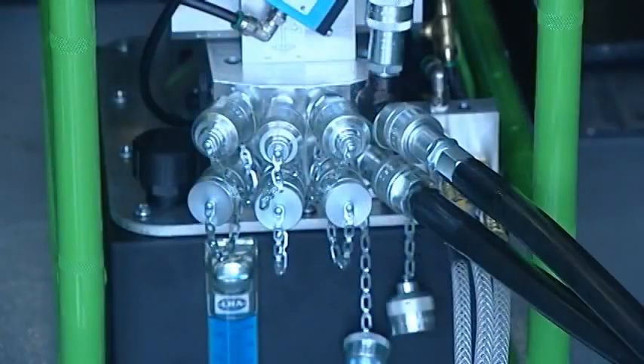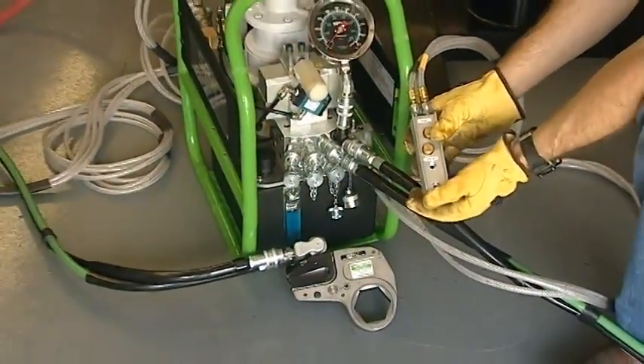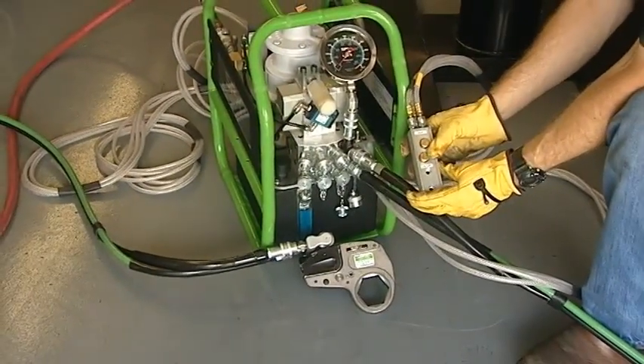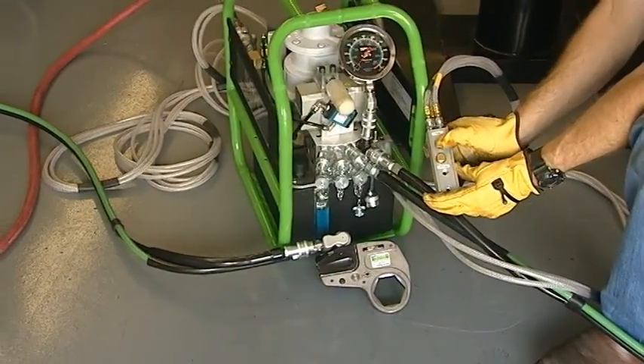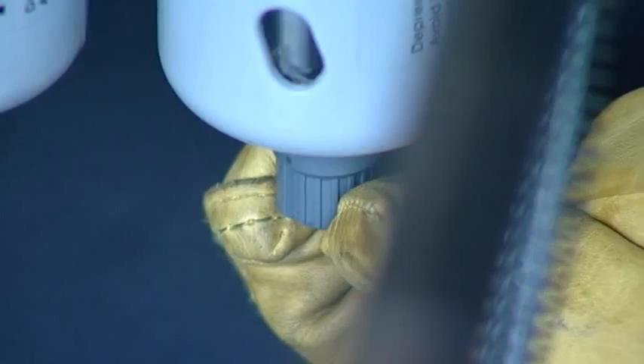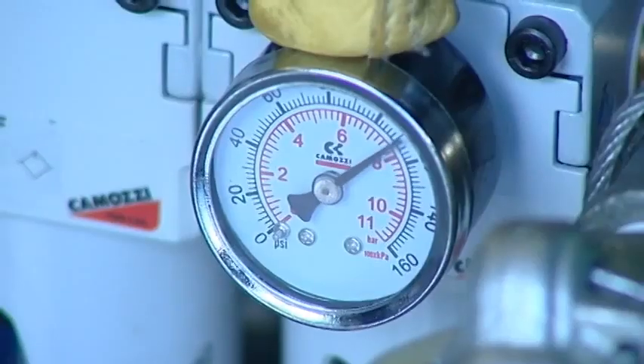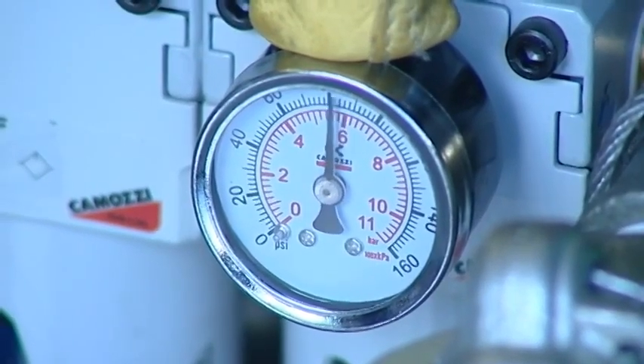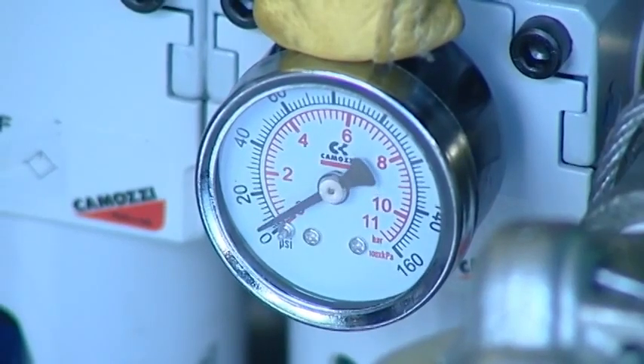Inspect the entire system for leaks. If a leak is discovered, never touch it with your hands. This could cause serious injury by hydraulic injection. Shut down the entire system and retighten fittings if necessary, or refer to the troubleshooting guide to resolve the leak. Remember to look for leaks with your eyes, not your hands.